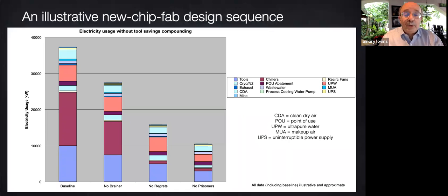The owner could also help his toolmakers save more than the roughly 70% shown in lavender for better tool design, chiefly by really mundane means like best-in-class vacuum pumps and power supplies, simply by telling the toolmakers what the savings were worth. And then we could probably do much better because tool loads cause most of the other loads. But this graph does not reduce those other loads correspondingly. If it did, the total savings in the right-hand bar would rise at least 4-fold from a base case that the client initially thought was already close to optimal, and clearly it wasn't.